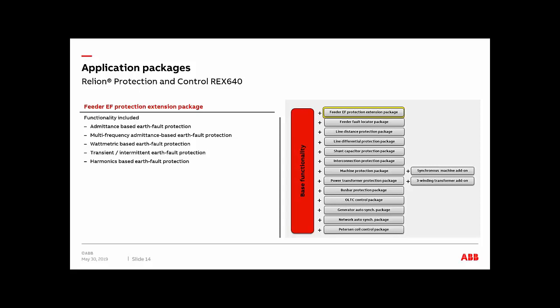And we have the transient or intermittent fault function, and this is mainly for situations where you have cables that have insulation failures. So this is a good way to detect them using the transient or intermittent one. And then we finally have the harmonic-based fault protection, which is simply a ground protection based on the harmonic content of the ground fault.